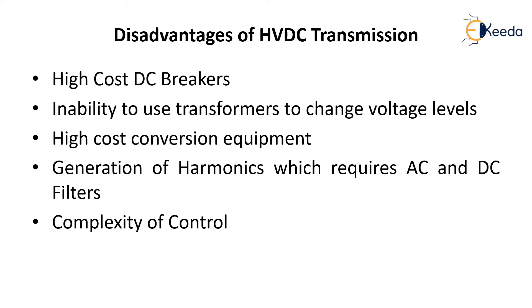The third disadvantage is the high cost of conversion equipment. Rectifier stations at the sending end and inverter stations at the receiving end are hugely expensive, which is why HVDC is used only for long-distance transmission — the cost is not viable for short-distance use. The fourth disadvantage is generation of harmonics. Harmonics must be filtered out using AC and DC filters, otherwise they affect both consumers and generating stations. Finally, there is complexity of control in HVDC systems, requiring specialized equipment.